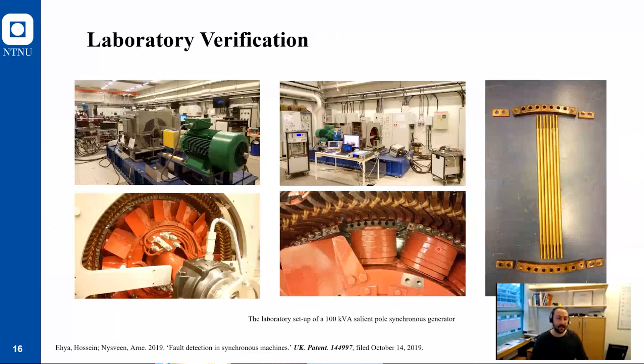The next step is to verify the idea in a laboratory. We have a really advanced setup in NTNU. It is a 100 kilovolt ampere salient pole synchronous generator. It resembles a typical Norwegian hydropower plant generator. It has 14 poles. We can apply different types of fault from short circuit, dynamic eccentricity, broken damper bar, broken end ring in this setup. The idea that we applied in this setup also worked really well. The results were very satisfactory, but as you know, in software and also in laboratory, everything is kind of ideal. So we need to verify in a real power plant.